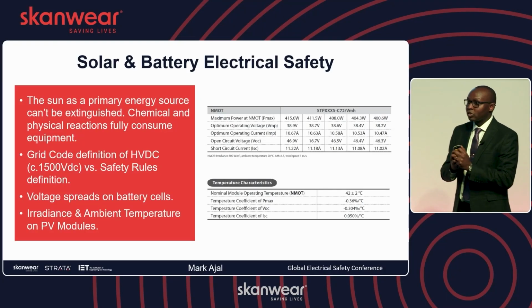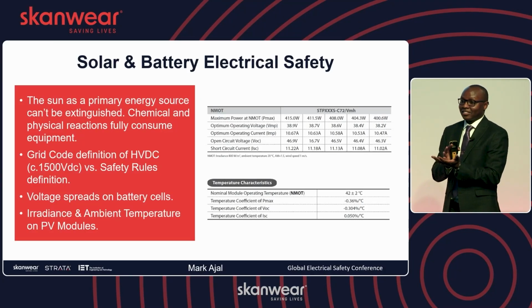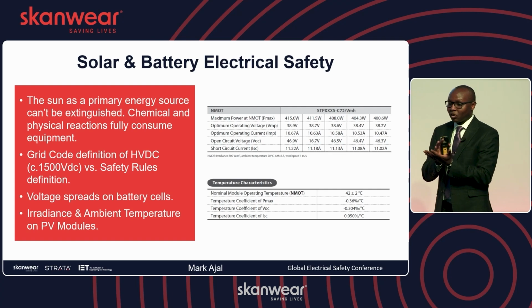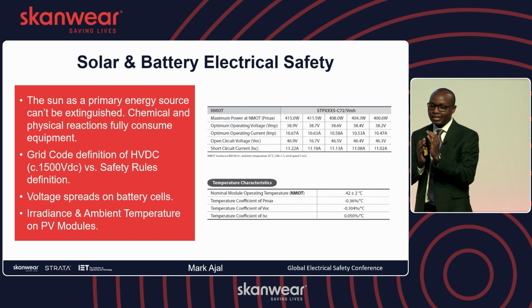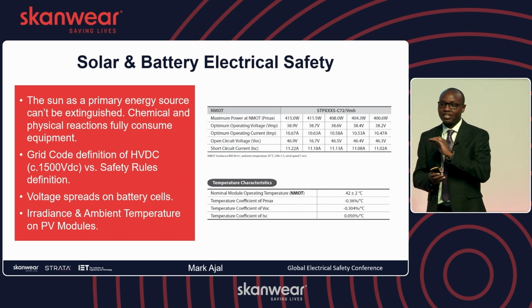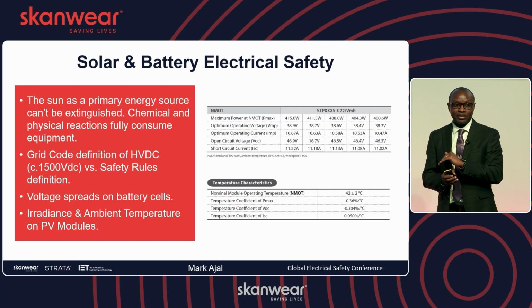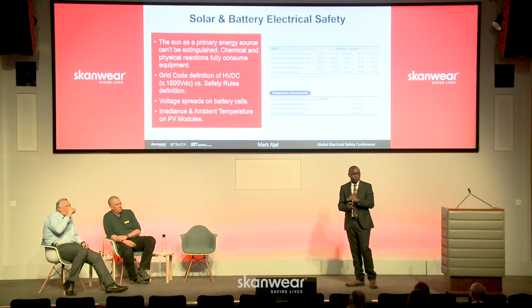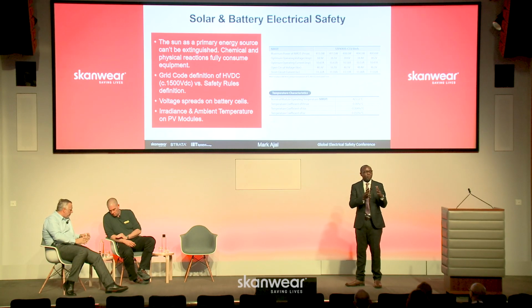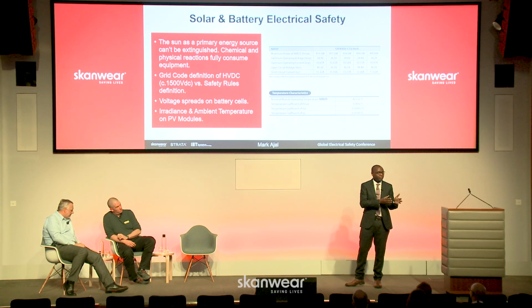Why do I say that? Some of these energy sources that we're dealing with in emerging technologies cannot be switched off. If you're looking at a solar farm, the moment those panels are exposed to the sun's irradiance, it's live. There's an open circuit voltage with a certain minimum watts per square meter of irradiance on the surface of the panel. You can't switch off the primary energy source, which is the sun. So where do you take your safety into the rest of the conversion system?